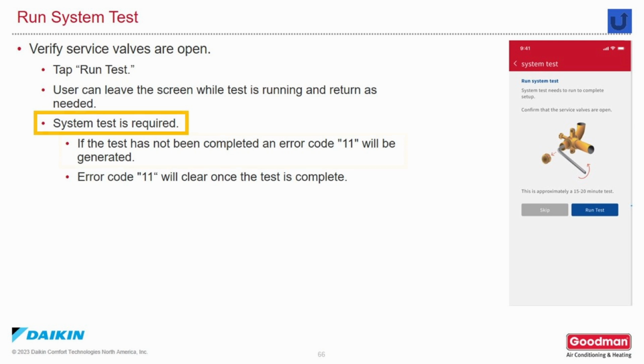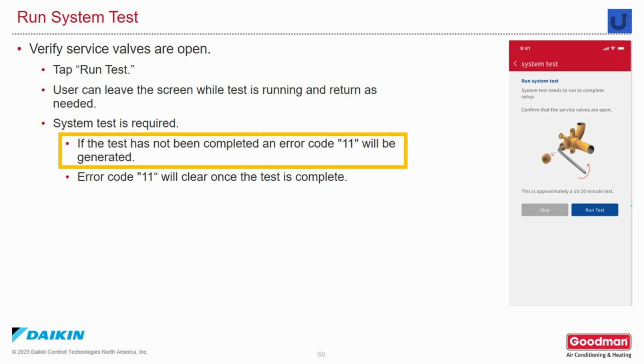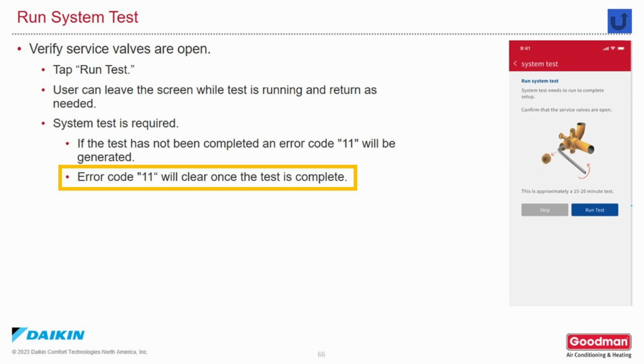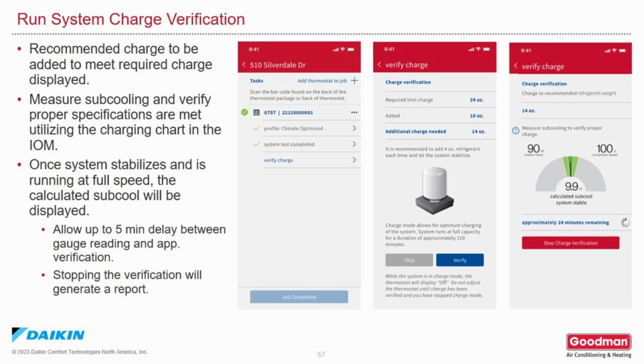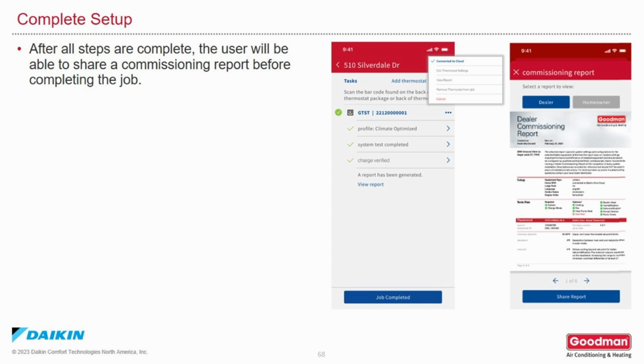System test is required. If the test is not completed, an error code 11 will be generated, but error code 11 will clear once the test is complete. When you run the system charge verification, the recommended charge needs to be added to meet the required charge that's displayed. Measure subcooling and verify proper specifications are met using the charging chart in the IOM. Once a system is stabilized and is running at full speed, the calculated subcool will be displayed. Give it up to a 5-minute delay between gauge readings and the app verification. Stopping the verification will generate a report. After all the steps are complete, you can share a commissioning report before completing the job.